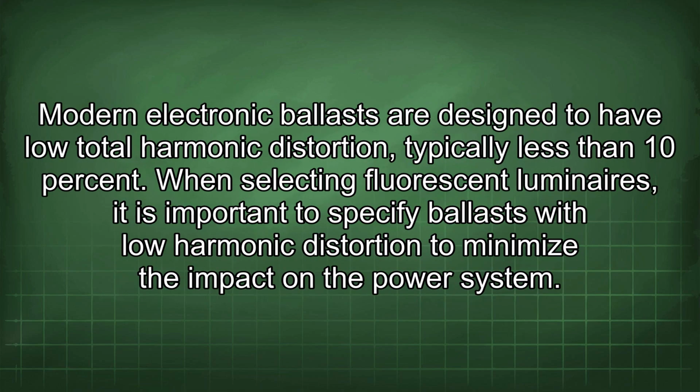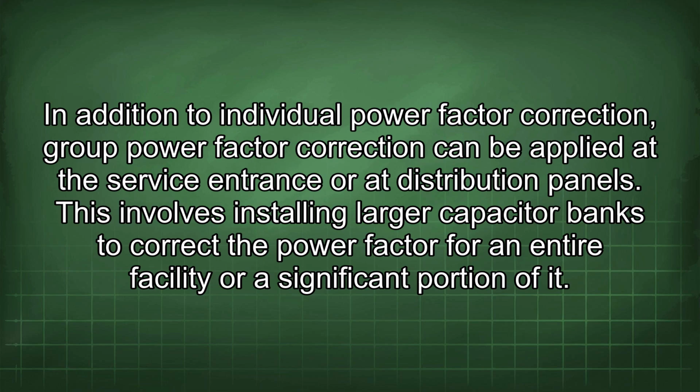Modern electronic ballasts are designed to have low total harmonic distortion, typically less than 10%. When selecting fluorescent luminaires, it is important to specify ballasts with low harmonic distortion to minimize the impact in the power system.